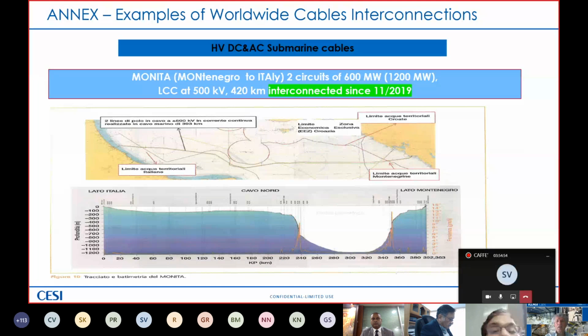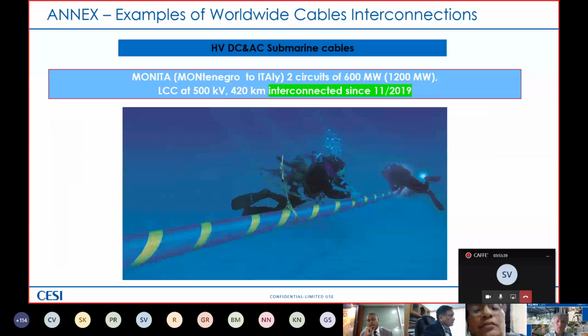Here again, it's another cable. This is already under voltage. The name is Monita, Montenegro to Italy. It's a two-circuit of 600 megawatt, so in total 1,200 megawatt, 420 kilometers. Here you can see that again you have a situation of low depth. Then you have a kind of basin where you need a different cable, and then this is the Adriatic Sea in the middle. Then near Montenegro, you come back to low depth again. And this has been interconnected since November last year. There are some pictures taken during the laying.